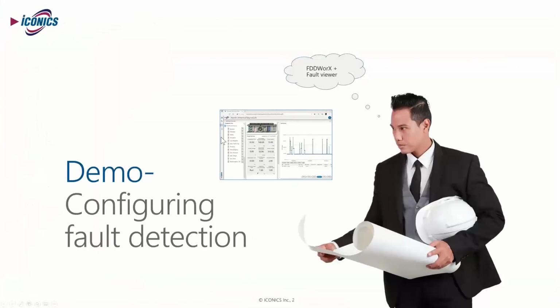We can do much more complex ones, where you're pushing the fault into an AI or ML model that comes up with far more sophisticated diagnoses. But generally speaking, most faults don't require AI or ML to come up with a potential root cause. The engineers who are setting this up can say, okay, when that happens, 9 times out of 10, the fan belt has broken or something.